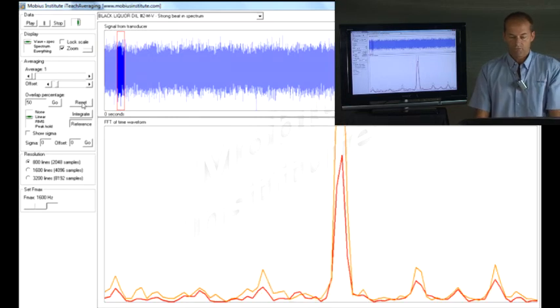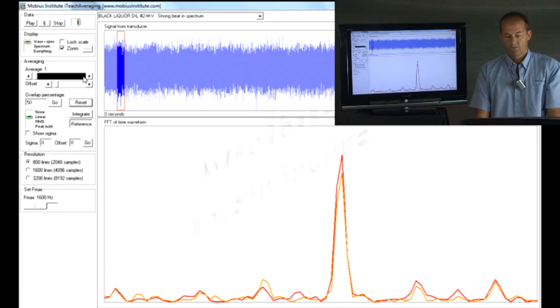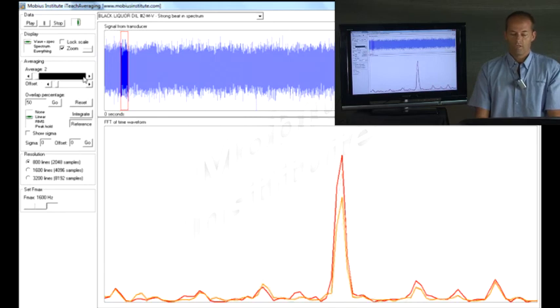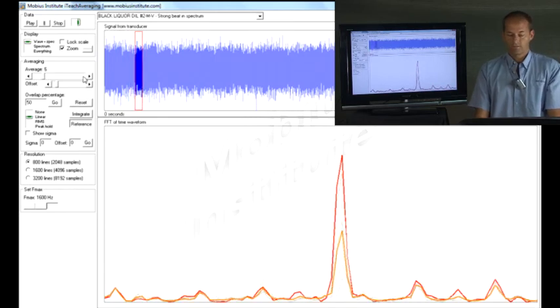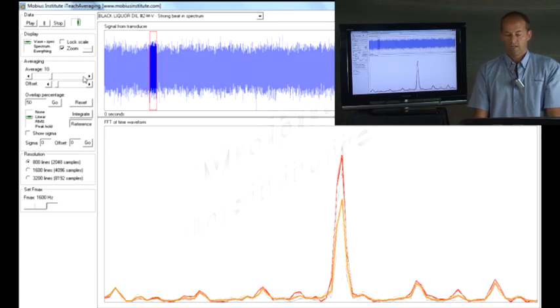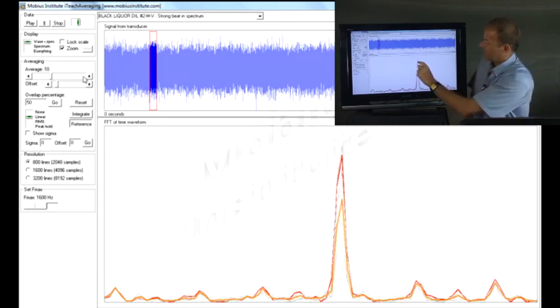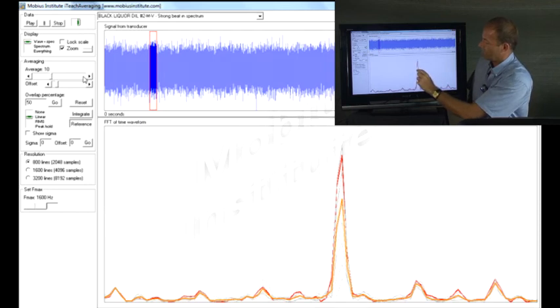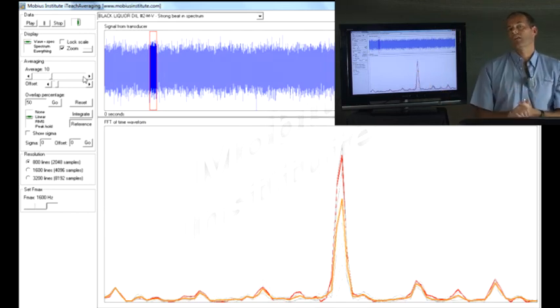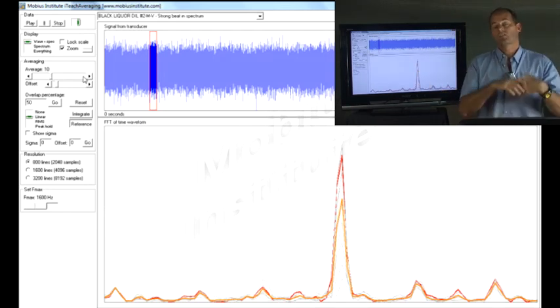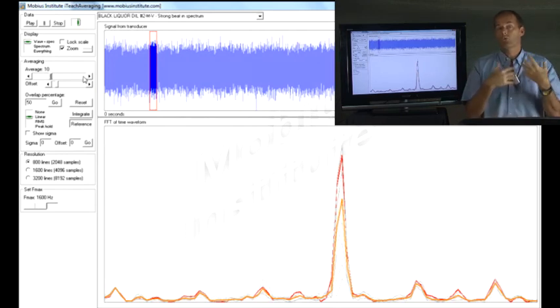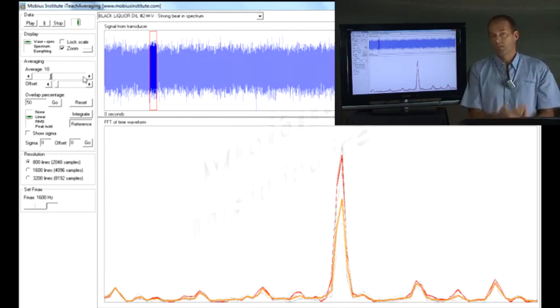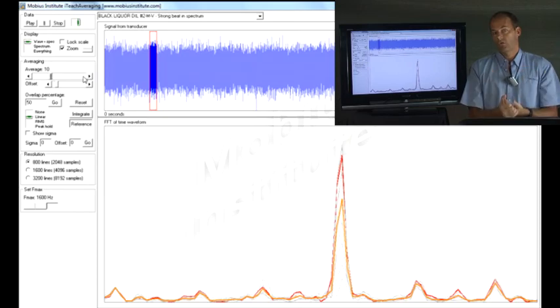And then go through again and choose one, two, three, four, five, six, seven, eight, nine, ten. Okay, it's not exactly right. In fact, that red line didn't draw in the right place. The two orange lines are around about in the same place. So if I take 10 averages, I will get repeatability. If I use four averages, I will not.